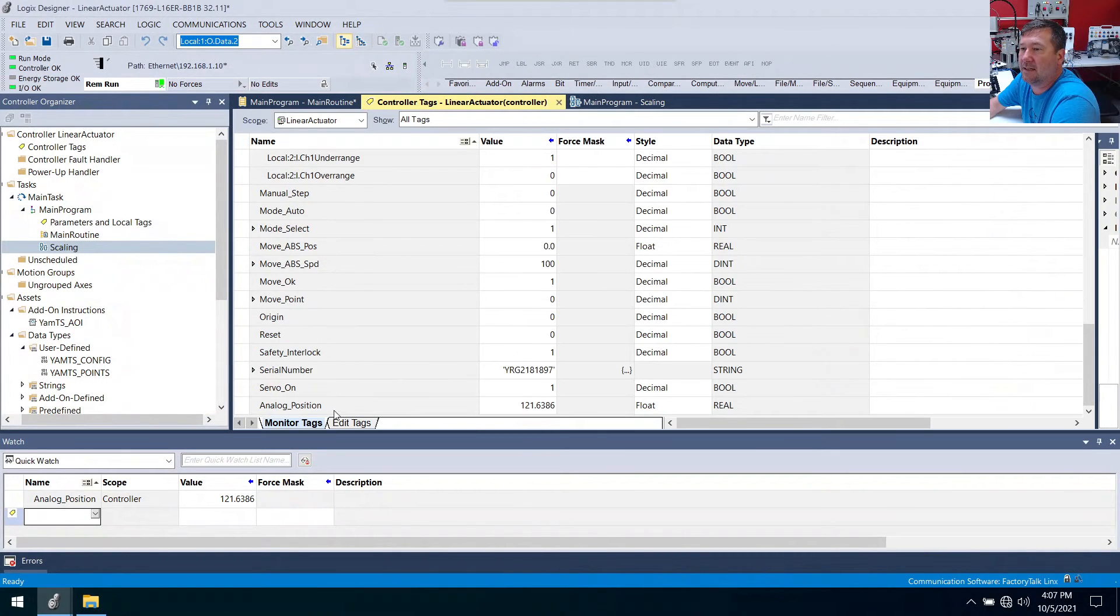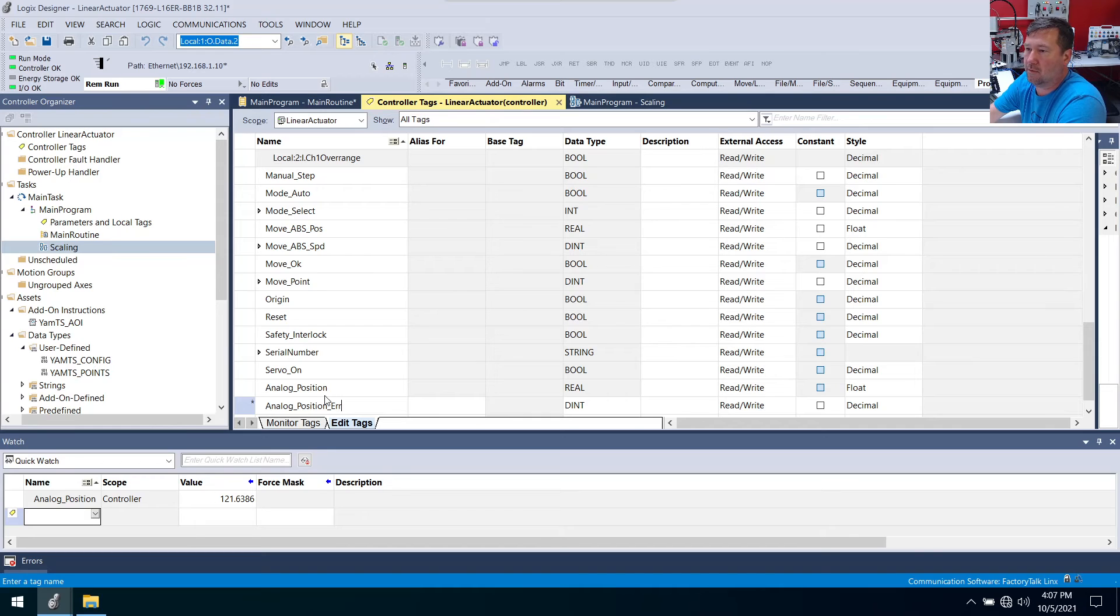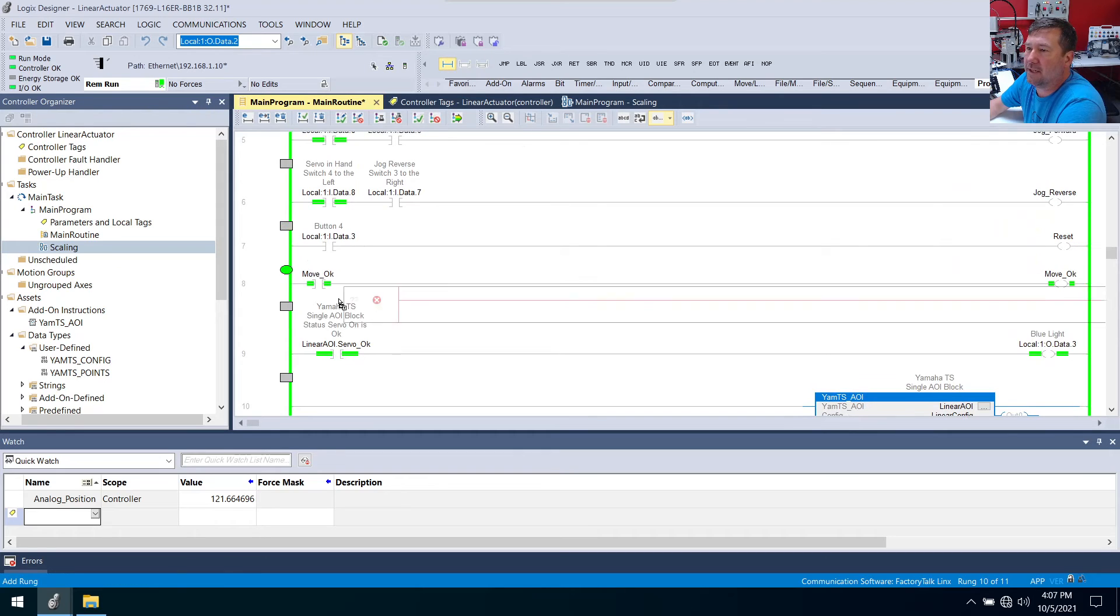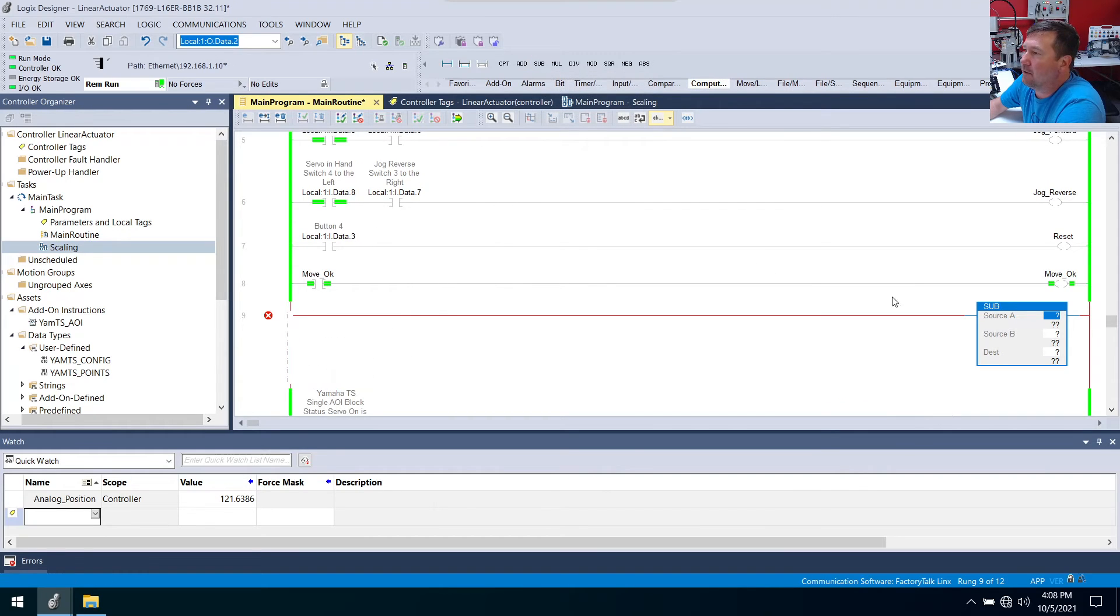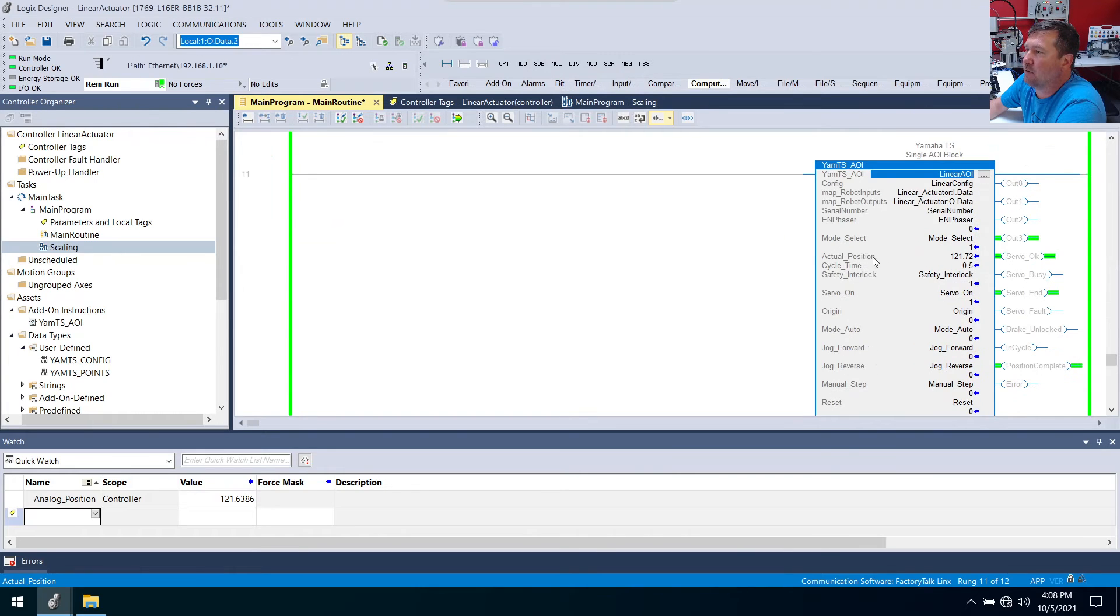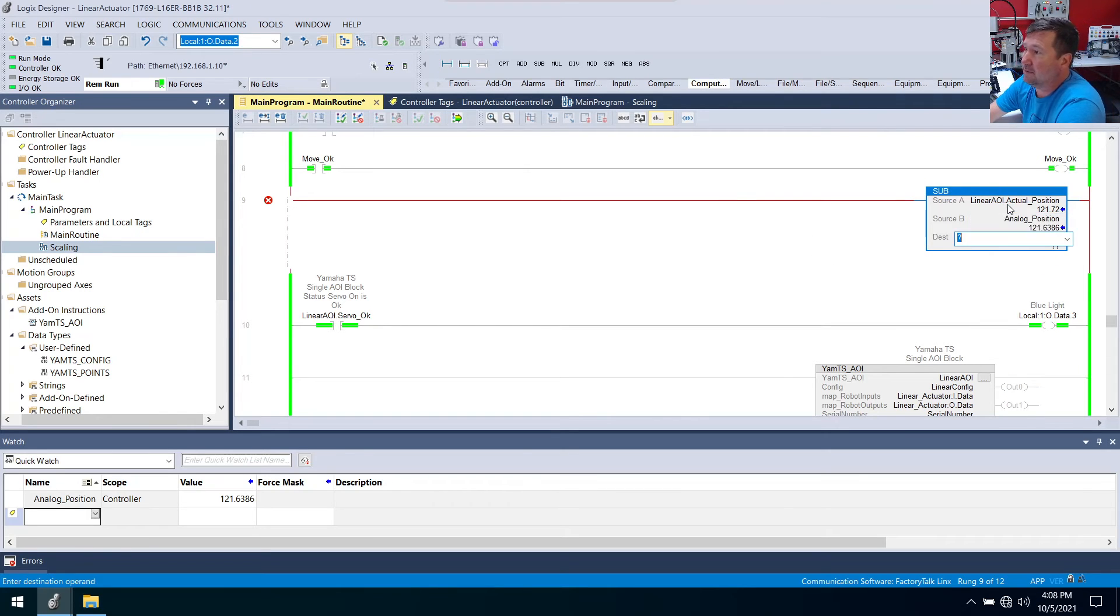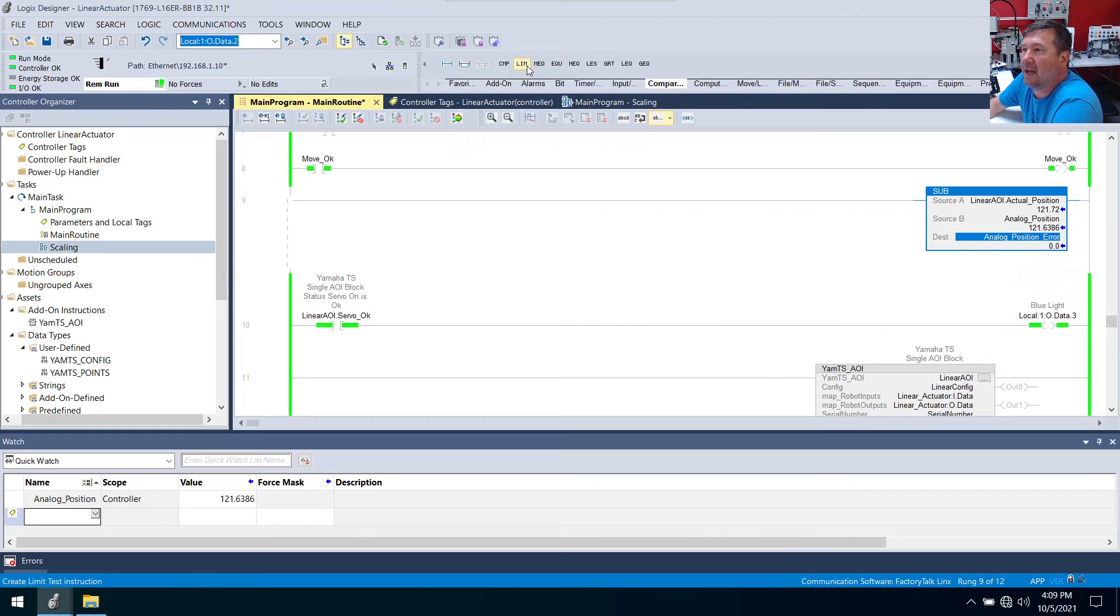So now let's make it where we can compare the two positions and see if we're in a certain range. So what we're going to do now is let's go and put in our controller tags. Let's go to edit. And we're going to add, let's call it our analog position error. And we want that to be a real. And now let's get our main routine. And right above the blue light, let's bring in a rung. And let's go to the compute math tab and let's bring down a subtract.